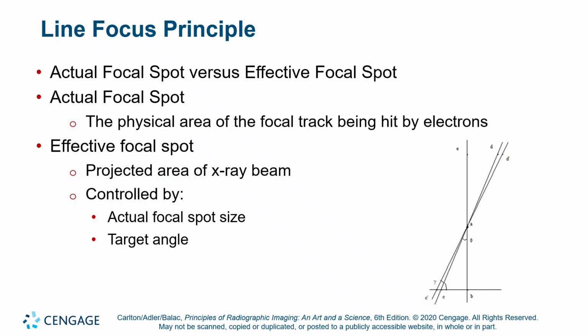Dual filament tubes sometimes have dual bevels, where the small filament has a very shallow bevel, a small tube angle, or target angle, but the large focal spot has a larger target angle. So I think we do have a dual bevel X-ray tube, an X-ray target anode, freestanding in the resource materials in the front of the classroom. So I'll be sure to show you that.